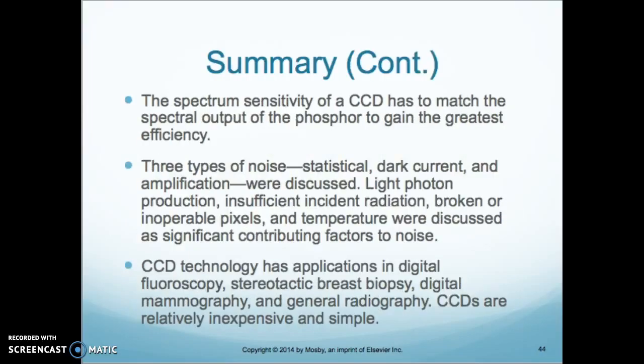The spectrum sensitivity of a CCD has to match the spectral output of the phosphor to gain the greatest efficiency. There are three types of noise: statistical, dark current, and amplification. Light photon production, insufficient incident radiation, broken or inoperable pixels, and temperature were discussed as significant contributing factors to the noise that is seen.